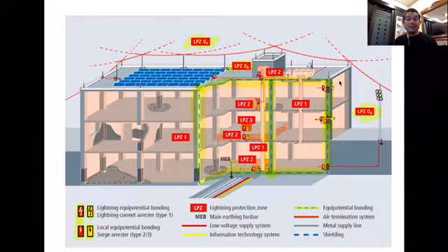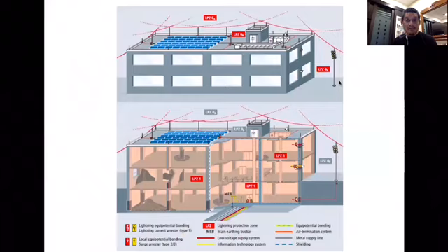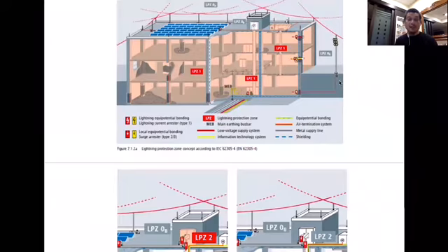For example, Z3 there, zone 3, could be just a cabinet where you put another SPD, like in the previous example. Before the equipment, we put another SPD. So the equipment there becomes Z3. Z2 is maybe the switchboard, and Z1 is actually at the main board. Okay, so this is another example to see how the structures, the locations, and so on.